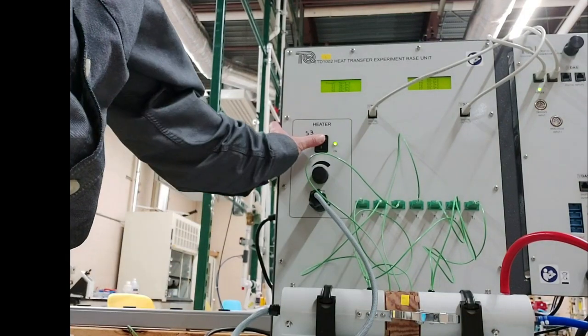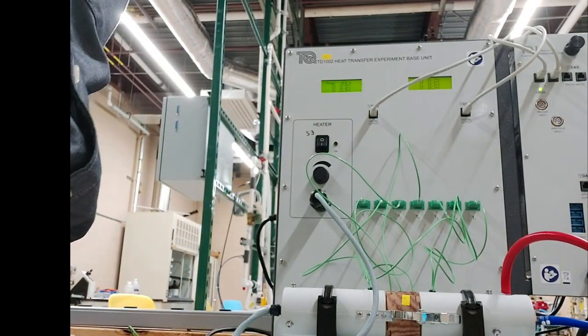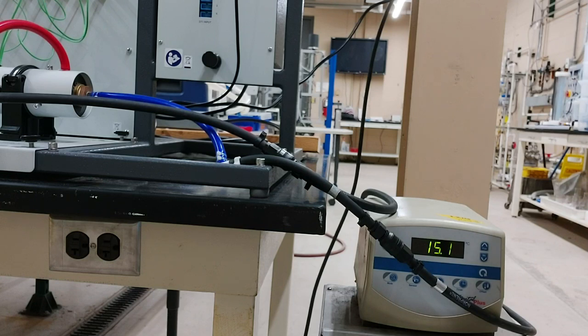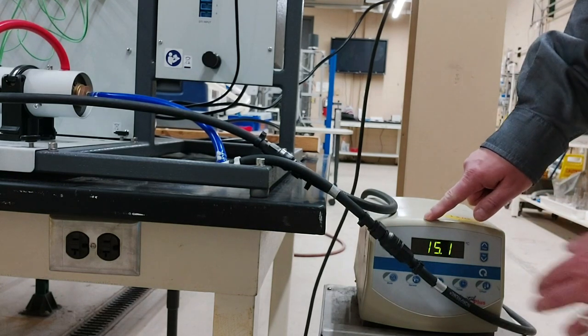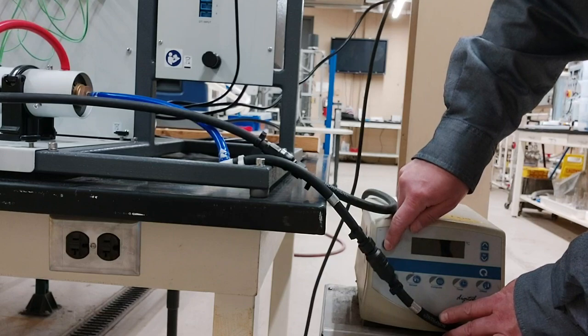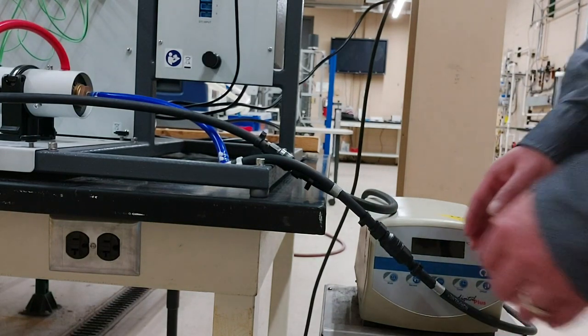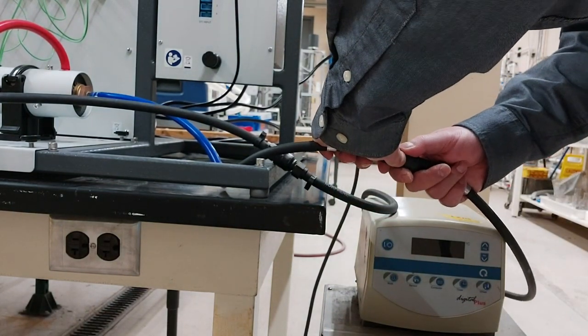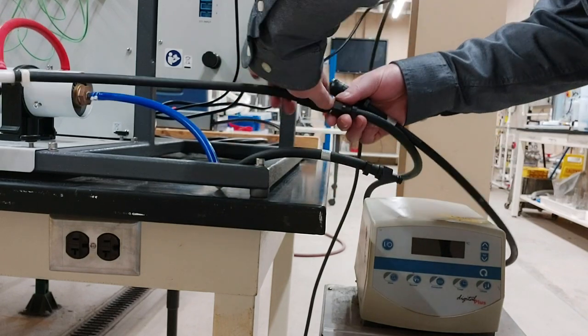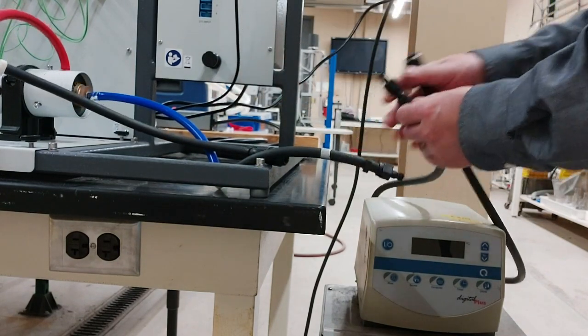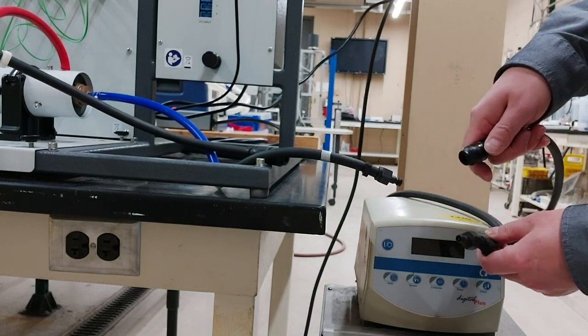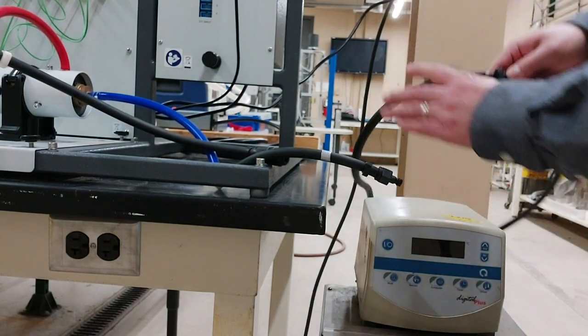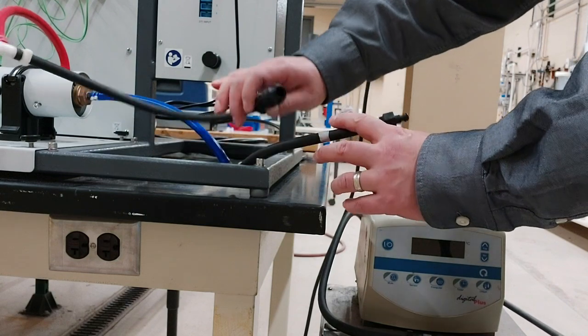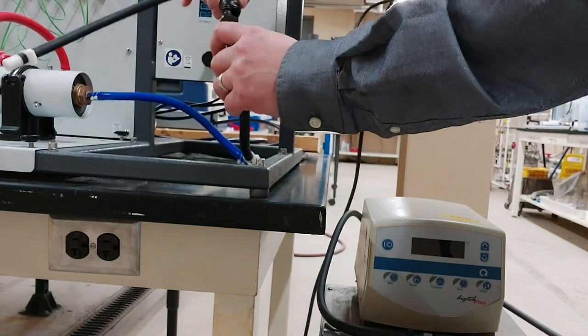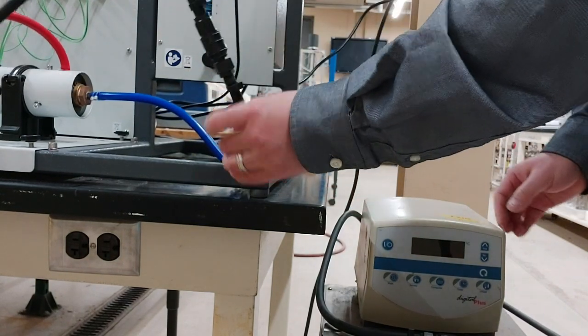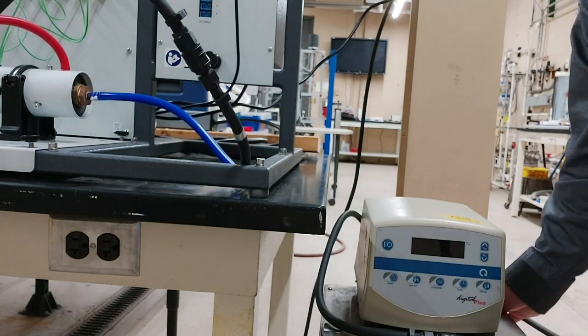When you are done with all trials, turn off the heater. Turn off the chiller. You do the startup procedure backward. First, turn off the power. Disconnect the water tubes. And connect chiller's water tubes to each other. Then connect instrument samples water tubes to each other. And move the water chiller backward a little bit.